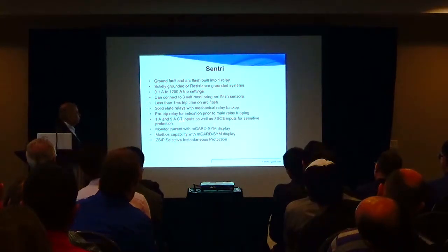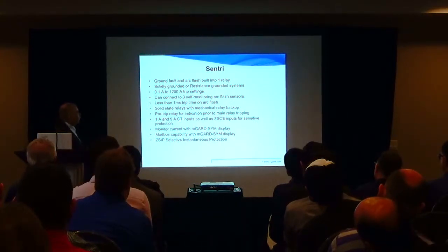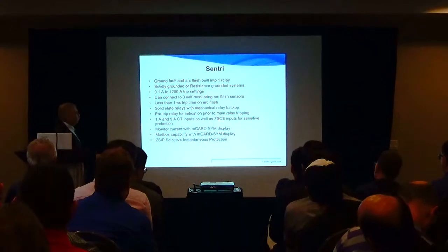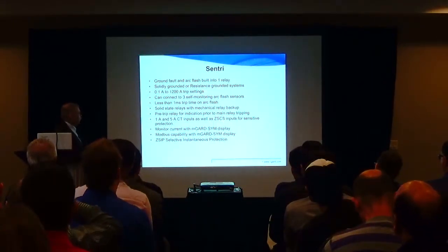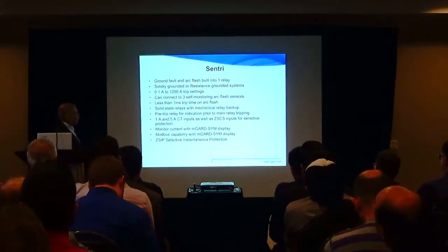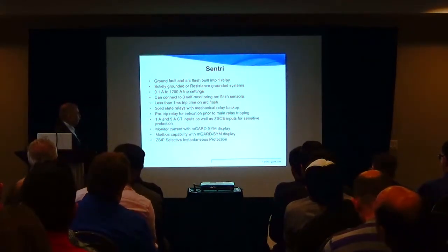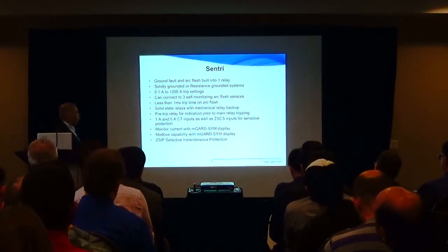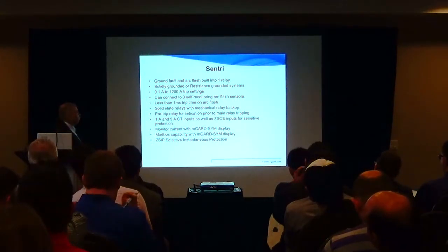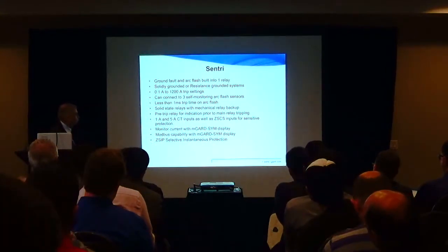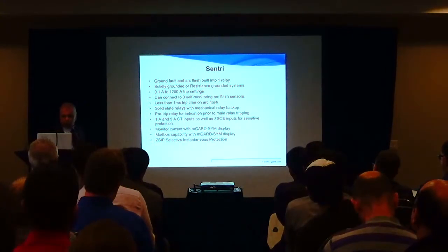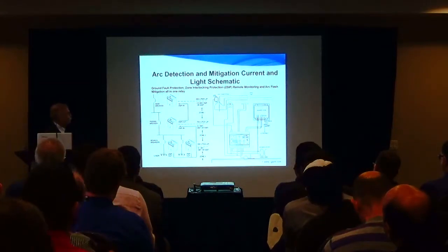It also accepts residually connected 1 amp or 5 amp CTs for solidly grounded systems. It also accepts zero sequence sensors for sensitive ground fault protection, 100 milliamps and so on. It monitors on the display unit, and the display unit has a Modbus capability to bridge to whatever other protocols you have to use, Ethernet or Profibus or DeviceNet, and so on. It also incorporates zone selective interlocking for solidly grounded applications. So it's a multifunction protective relay.